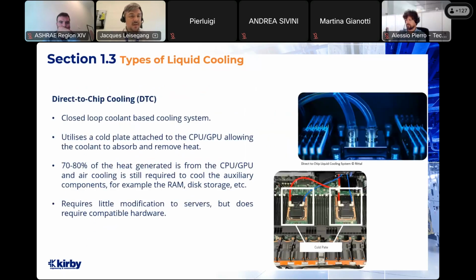So firstly, direct chip cooling. In a direct to chip system, it's a closed loop coolant cooling system that utilizes a cold plate. There's a cold plate attached to the CPU or the GPU, and the fluid runs into the cold plates and absorbs and removes heat directly from them.